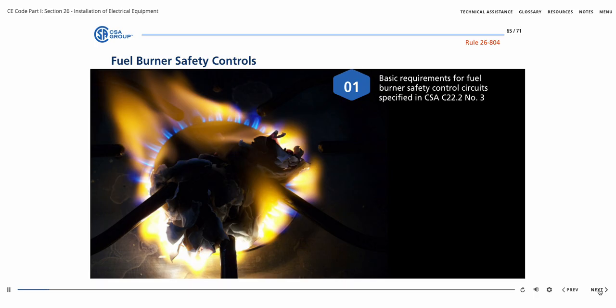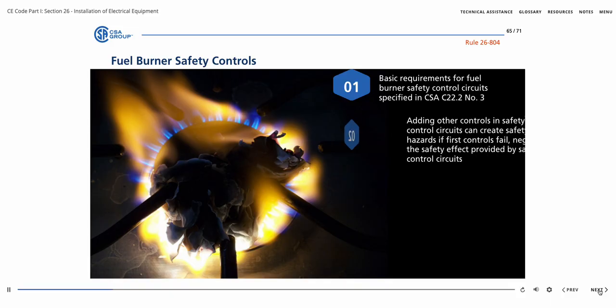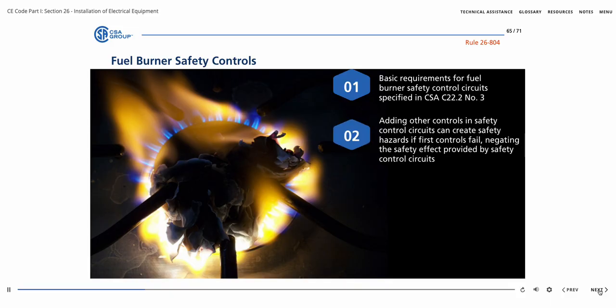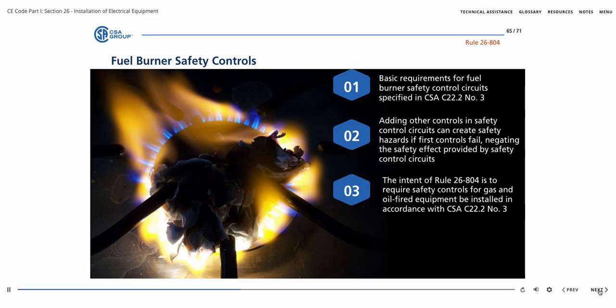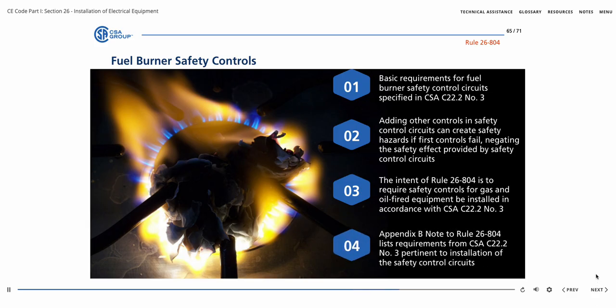Some of the basic requirements for fuel burner safety control circuits are specified in CSA C22.2, number 3. The addition of other controls in the safety control circuits can create a safety hazard if these controls fail, thus negating the safety effect provided by the safety control circuits. The intent of Rule 26-804 is to require safety controls for gas and oil-fired equipment to be installed in accordance with CSA C22.2, number 3. Appendix B, note to Rule 26-804, lists the requirements from CSA C22.2, number 3, pertinent to installation of the safety control circuits.